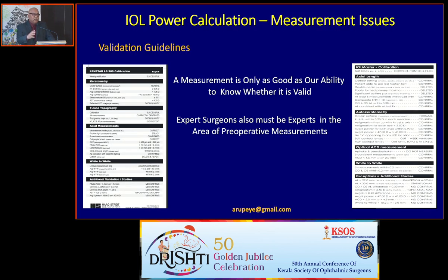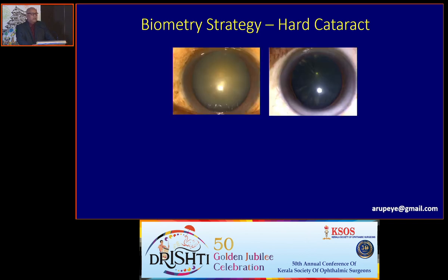Even if you're using an optical biometer, please remember that the validation guidelines still work. If you get results which are tagged red, you may have to delete those results and repeat the measurements. For hard cataract situations, some of those older optical biometers do not give any value.